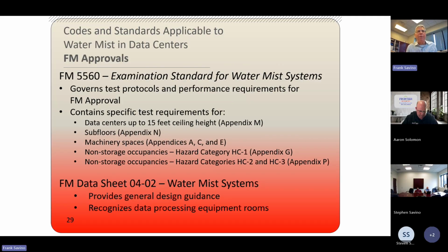It's titled Examination Standard for Water Mist Systems, and it governs test protocols and performance requirements to get FM approval. And it has specific test requirements. And by the way, you can find the FM standards right online. If you just Google Factory Mutual FM standard 5560, you'll find it very easily, okay? So it'll tell you all the different test requirements for the different, what they call appendices. So for example, data centers up to 15 feet in height is Appendix M. It describes the hazard, but more importantly, it describes the test that somebody who wants to get a listing or approval has to pass, okay? So that's right there in Appendix M.